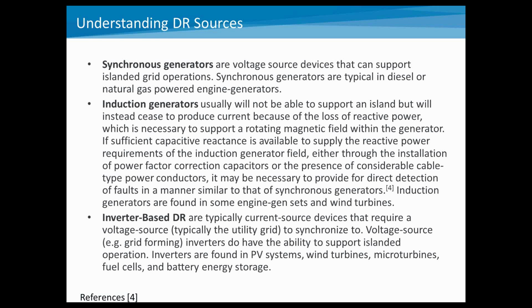And then finally, inverter-based distributed resources. This is something that's becoming much more prominent with things like photovoltaic systems or energy storage systems, where you have an inverter-based system. Now, typically, in general, you need a grid-forming inverter to provide that support, so a voltage source-based inverter system. A lot of times now, these inverters are operating in a current control mode, and so they aren't necessarily able to provide a voltage source, but are phase locked into the AC power system.